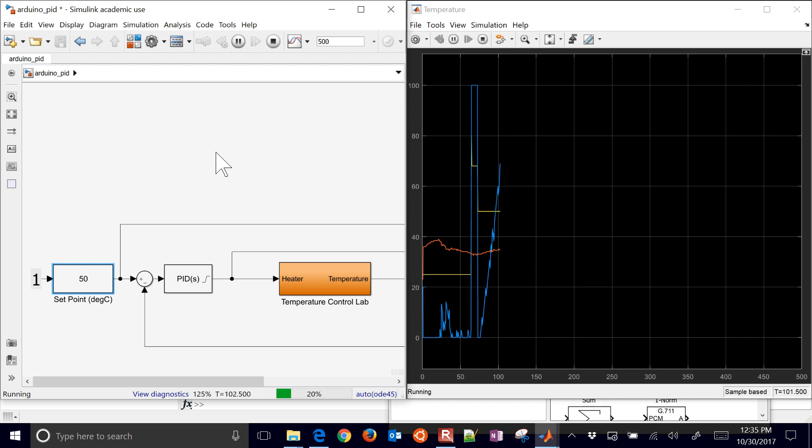So it's going to be coming up. There's my heater value that's coming up. I'm not sure if this is the anti-windup that's doing some funny things there. I don't normally expect it to do what you saw in the blue value. But you can put in whatever you want there for your PID controller, and then it will hopefully respond. I have my blue line, my heater, going up. And you can see the orange, which is the actual temperature, that's starting to increase toward the setpoint. And then we want to see it get up to the setpoint and hug that there. Try to maintain the certain setpoint. I want to get the yellow and the orange lines to match up.